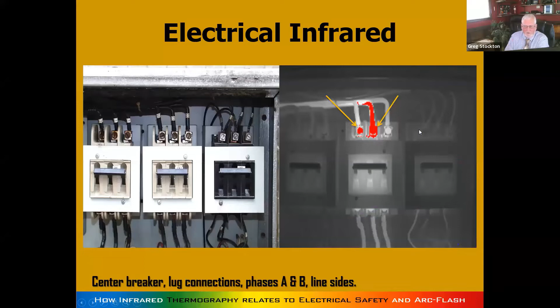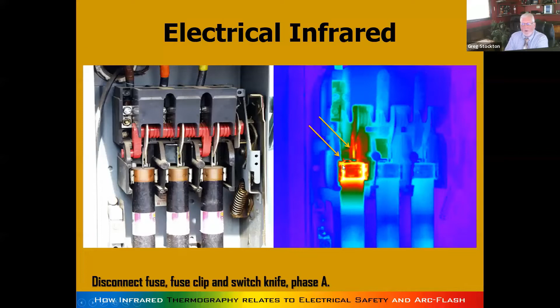Probably the most common thing, if you took all the millions of things found every year by infrared cameras in switchgear in every building across the United States and Canada and everywhere, these fuse clips are probably the most common, along with breaker lugs and loose wires.